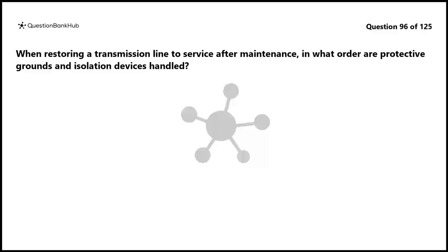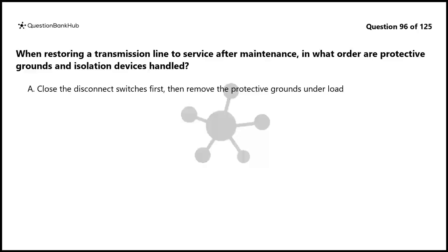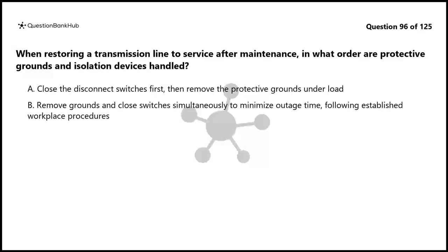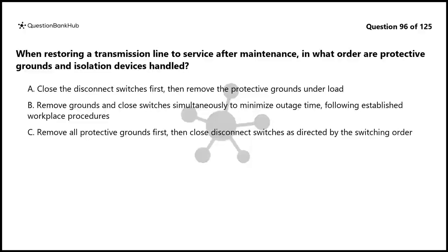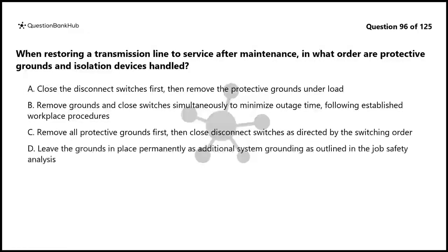Question 96. When restoring a transmission line to service after maintenance, in what order are protective grounds and isolation devices handled? A. Close the disconnect switches first, then remove the protective grounds under load. B. Remove grounds and close switches simultaneously to minimize outage time, following established workplace procedures. C. Remove all protective grounds first, then close disconnect switches as directed by the switching order. D. Leave the grounds in place permanently as additional system grounding as outlined in the job safety analysis.